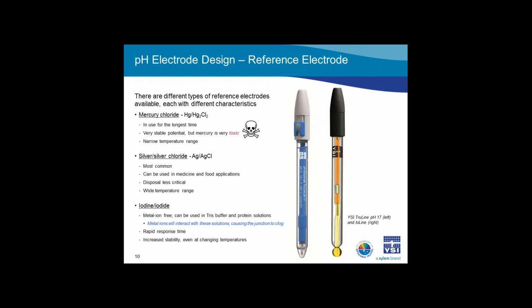The iodine-iodide system is a relatively new reference electrode that has several important advantages over other electrodes. This reference is metal ion-free, which is very important when measuring in tris buffer and protein solutions. Reference electrodes like silver-silver chloride have metal ions that will negatively interact with these solutions, resulting in the reference junction becoming clogged. The iodine-iodide electrode also has a low temperature dependence that allows for rapid response time. Also, the stability of this reference, even at changing temperatures, results in excellent measurement stability. The unique color of the YSI iodine reference can be seen here on the right.